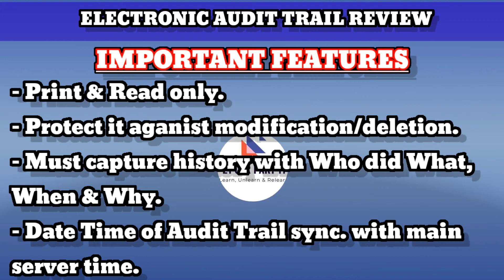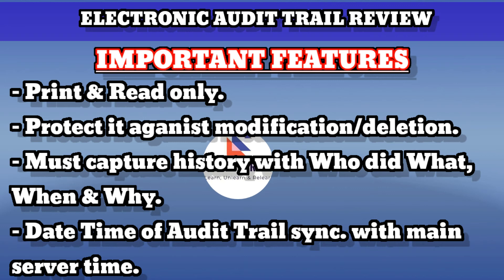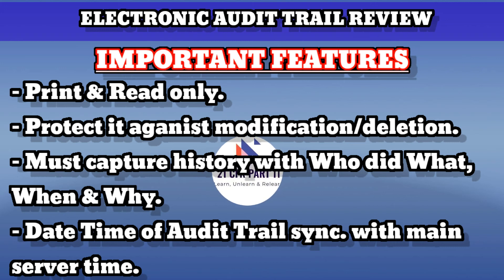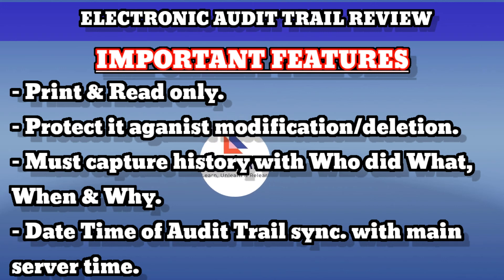Some important features that an audit trail must have are as follows: access to audit trail data should be limited to print or read-only purposes; it must be protected against modification or deletion; it should capture a full history of all GMP-related transactions including the identity of the person making the change — in short, who did what, when, and why. The audit trail date and time must be synchronized with trusted date and time services such as the main server, and it should be readily available in a readable format.